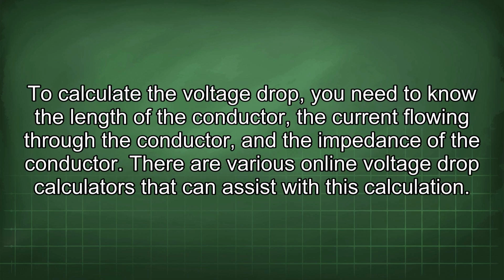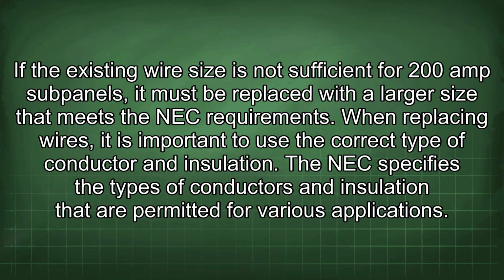To calculate the voltage drop, you need to know the length of the conductor, the current flowing through the conductor, and the impedance of the conductor. There are various online voltage drop calculators that can assist with this calculation. If the existing wire size is not sufficient for 200 amp subpanels, it must be replaced with a larger size that meets the NEC requirement.